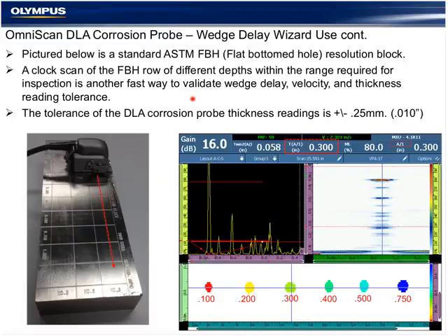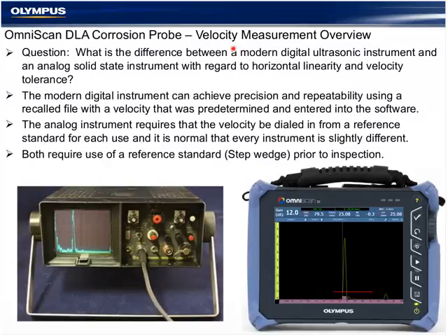In this case, the A-scan is fixed, but I could put it in track mode and slowly walk it across the same calibration standard for a validation of each A-scan on each flat-bottomed hole for a validation of the thickness measurements. So what is the difference between a modern digital instrument and an analog solid state instrument with regard to horizontal linearity and velocity tolerance? A lot.